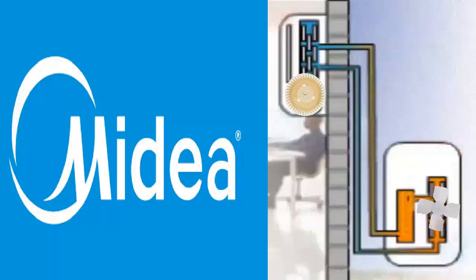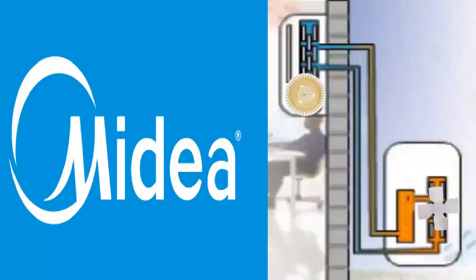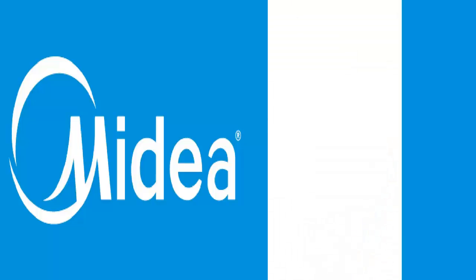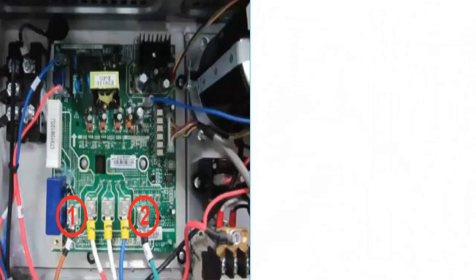The following describes the error codes identified with the letter L in Midea brand air conditioning units, along with their meanings, and then we will go over the steps to follow for their diagnosis. The code L0 indicates a problem with the compressor inverter module or the connection from the circuit to the compressor.